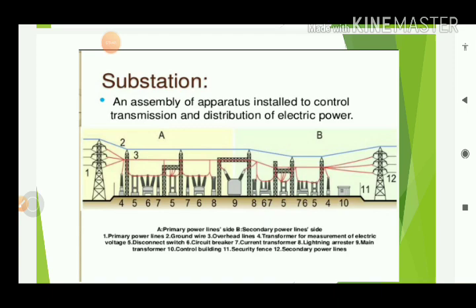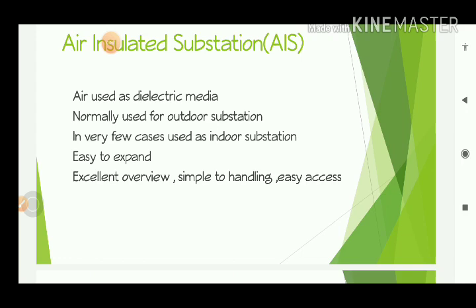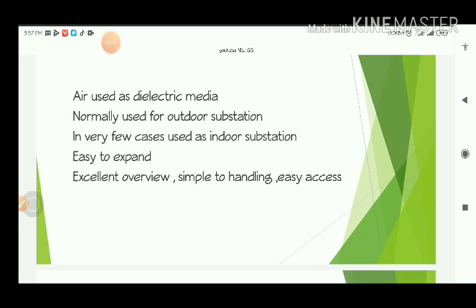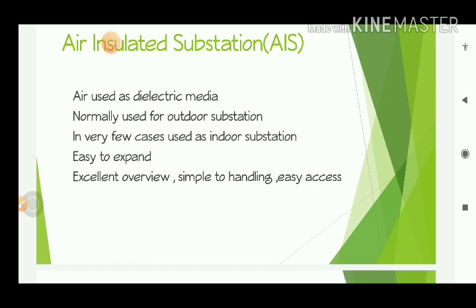The air insulated substation uses air as a dielectric medium. It is normally used for outdoor substations. In very few cases it is used indoors — for example, in highly populated areas or seismic aspects such as flood-affected or earthquake-prone areas. It is easy to expand for future expansion purposes. It provides an excellent overview, is simple to handle, and is easily accessible. These are all parts included in the air insulated substation.